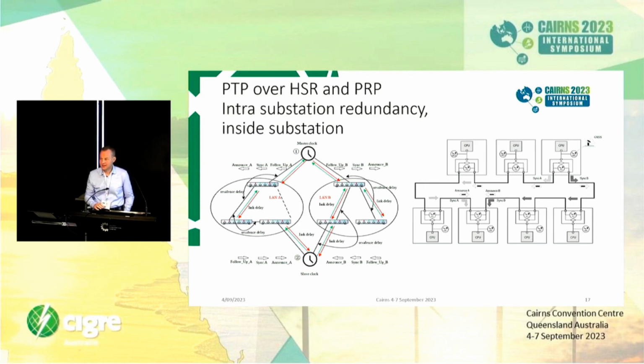If we're talking about the 61850-9-3 profile though, that's covered by 62439 part 3, I think. In that case, the slave clock actually runs the best master clock algorithm and looks at both incoming signals separately, which is a requirement of that standard. So in the end, the tiebreaker is the port number it's coming in on, if they've got the same accuracy and all other parameters match.